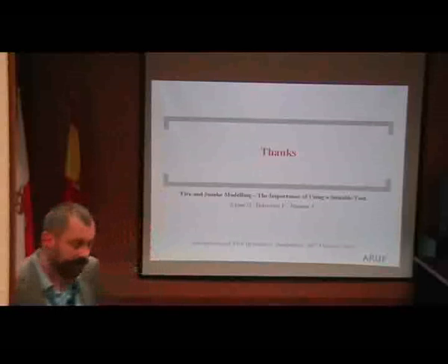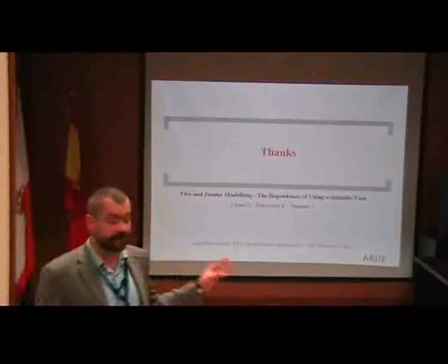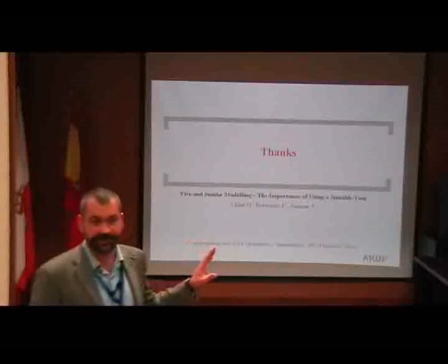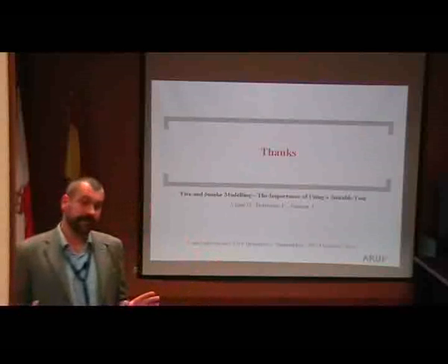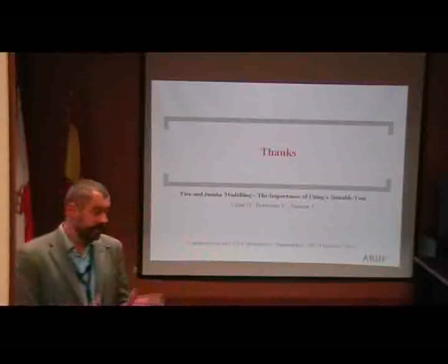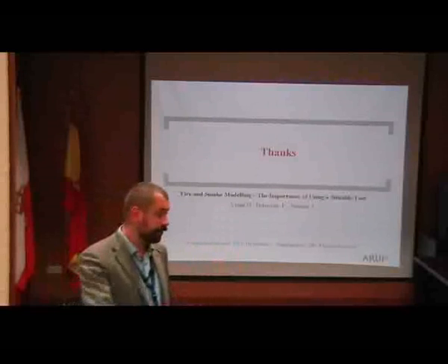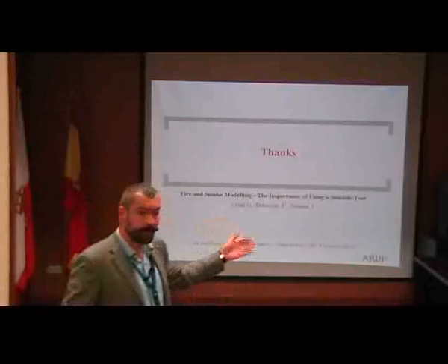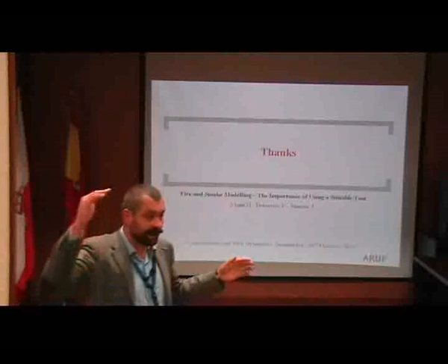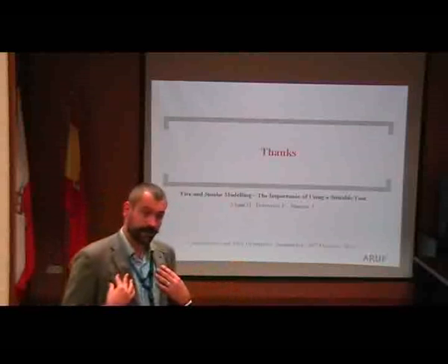What is your opinion? Well, my opinion is that you're absolutely right, and I have two answers. One is that I just showed that for a particular scenario FDS works. I can tell you that there are validations for particular scenarios in which FDS works. If I put a thermocouple just above the fire or the flame and have a fluctuation of 200%, that's clear it doesn't work. But 4, 5, 6 meters from the fire, close to the ceiling, it was okay. I mean, for our design purpose, it's okay.